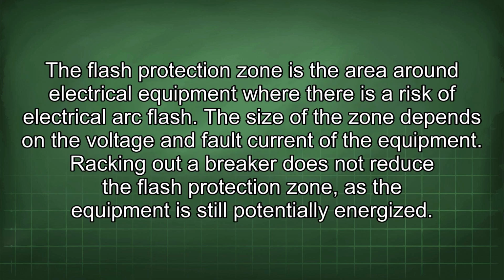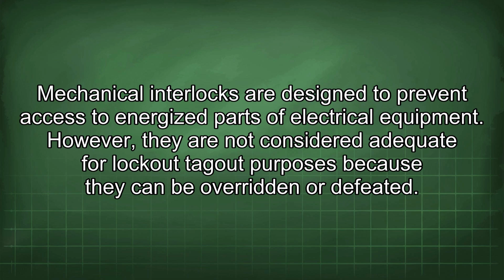The flash protection zone is the area around electrical equipment where there is a risk of electrical arc flash. The size of the zone depends on the voltage and fault current of the equipment. Racking out a breaker does not reduce the flash protection zone, as the equipment is still potentially energized. Mechanical interlocks are designed to prevent access to energized parts of electrical equipment. However, they are not considered adequate for lockout tagout purposes because they can be overridden or defeated.